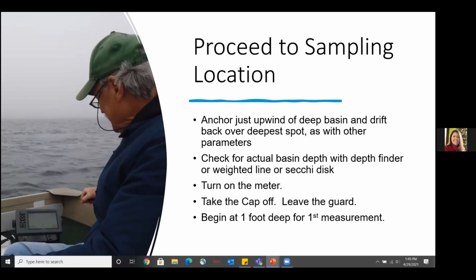Turn on your meter. Make sure it's warmed up. Take the cap off that has the sponge in it, but leave the guard on it, whether it be the silver guard or the black plastic guard. And then you'll start at 1 foot deep for your first measurement. So you'll just unspool your cord and go to 1 foot deep.